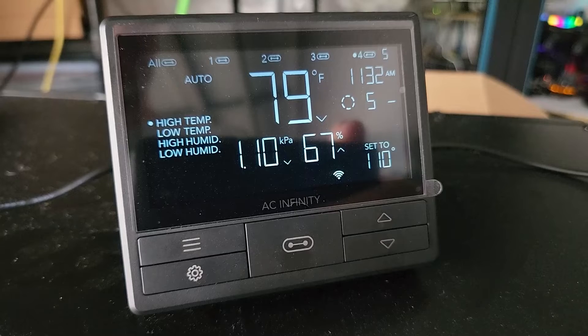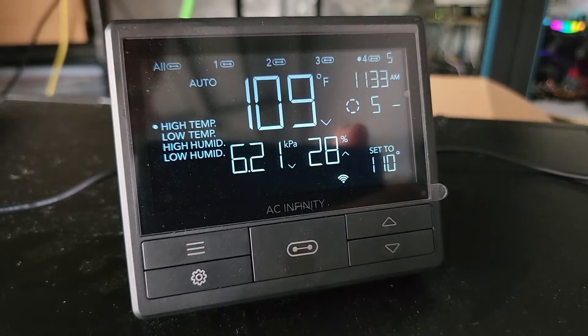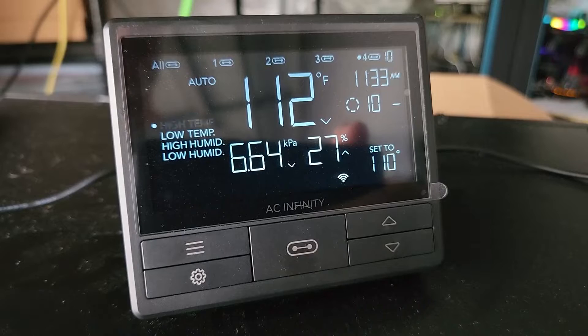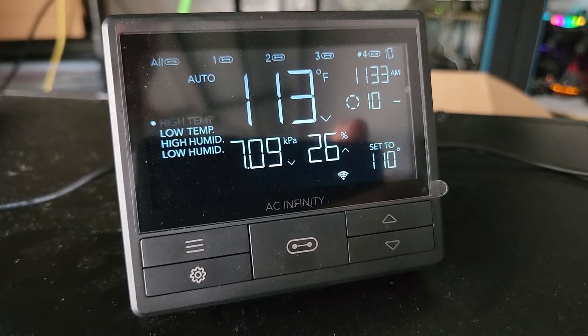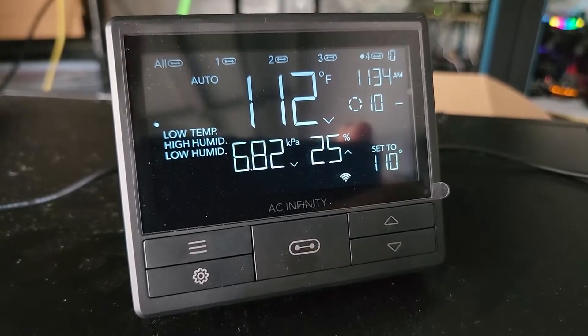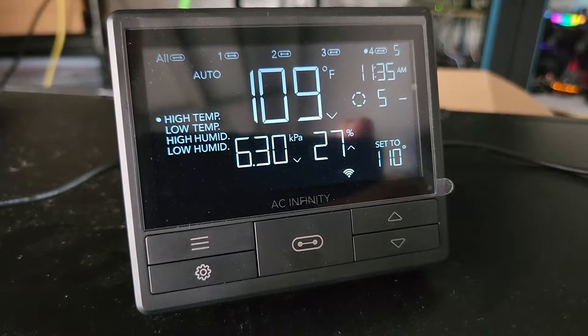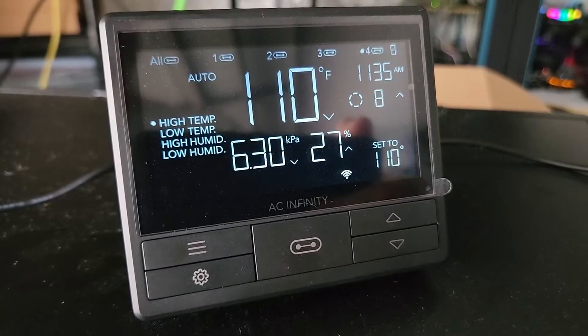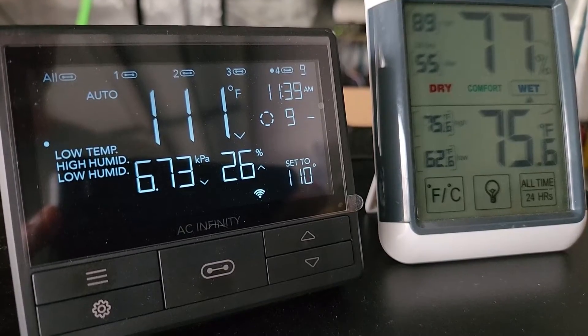We're back to hashing and the temperatures start to increase. The fan automatically kicked right up to 10. We'll see if it starts to back off after it gets cooled down — but it looks like it's going to require some tweaking because it just wants to jump between those two speeds.